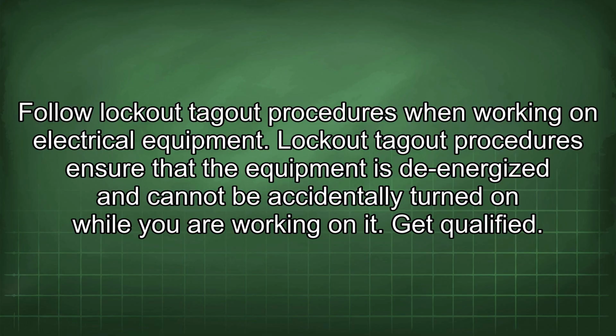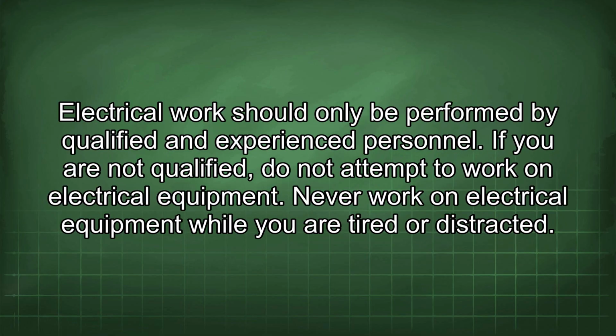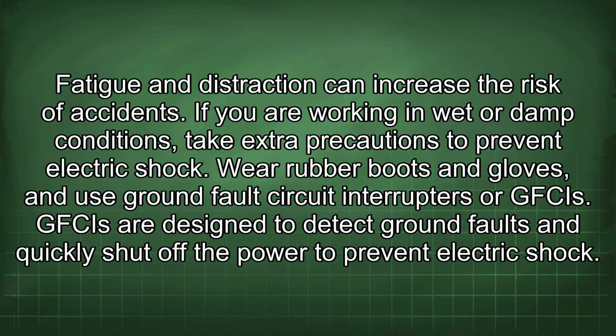Get qualified. Electrical work should only be performed by qualified and experienced personnel. If you are not qualified, do not attempt to work on electrical equipment. Never work on electrical equipment while you are tired or distracted. Fatigue and distraction can increase the risk of accidents. If you are working in wet or damp conditions, take extra precautions to prevent electric shock. Wear rubber boots and gloves and use ground fault circuit interrupters or GFCIs. GFCIs are designed to detect ground faults and quickly shut off the power to prevent electric shock.